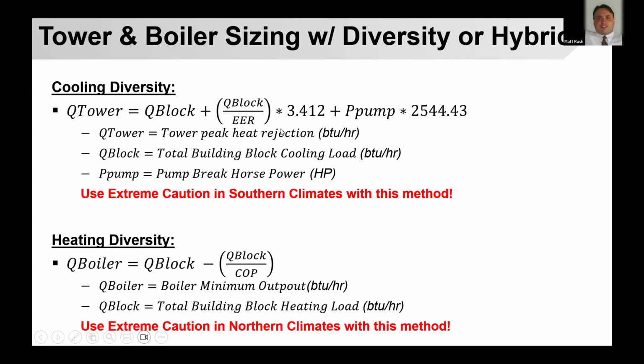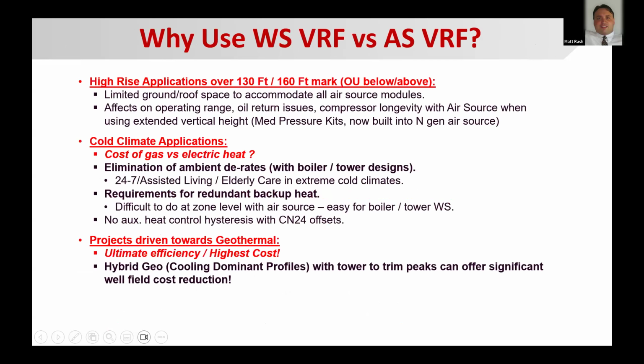This component here really is just your heat of compression. So it's your block load, whatever that worst case is, plus the heat of compression, plus some pumping energy that's imparted into that condenser water loop. For heating diversity, if you're going to size with a backup boiler, you would need to know that peak load, and then you can subtract off the heat of compression component. So that's really just your block load divided by the COP. And those values, the EER and the COP in cooling and heating, can be obtained from the manufacturer.